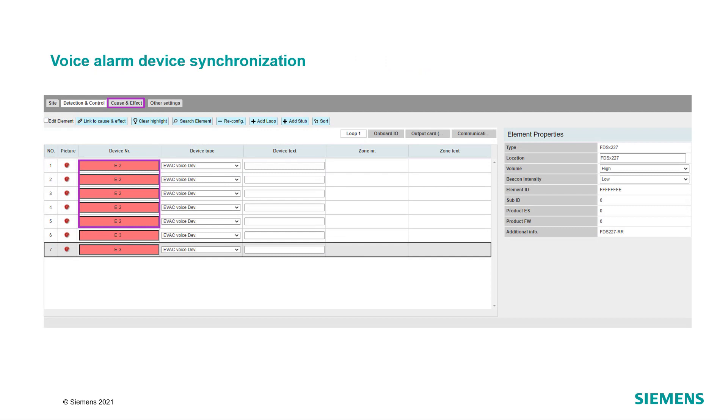By default, the synchronization takes place within voice alarm devices having the same device number. That means voice alarm devices with different device numbers are not synchronized. The panel guarantees that the synchronization within the same device number works if no more than 5 device numbers are used.